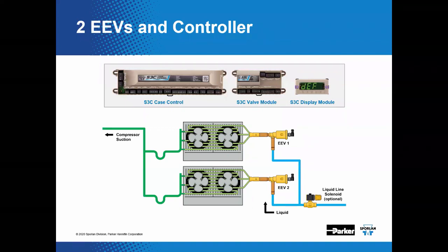Awesome. And again, the EEVs in this particular example will regulate superheat by using that temperature pressure approach. Correct. The controller will energize the optional liquid line solenoid valve, again through successive opened and closed positions in conjunction with the EEV, to control case temperature with that cut in and cut out method. You can always go back later and take a look at the sensor and transducer detail on the previous slide when you review the recorded version on YouTube or Facebook.